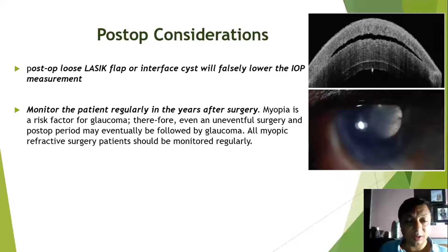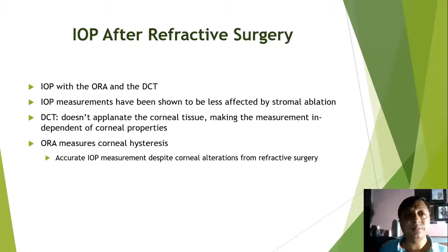Now, the Goldmann applanation has limitations. If you look at newer tonometers like the ocular response analyzer or the dynamic contour tonometer, they have a little advantage over the Goldmann. They have been shown to be less affected by the ablation. So DCT doesn't affect the corneal tissue, making the measurement independent of corneal properties, and ORA measures corneal hysteresis. So these two may be a better technology. Of course, we require more data because there is a lot of research going on on hysteresis, but it requires more data on how to use it in day-to-day practice. But they have the potential to be used in day-to-day practice for the longer term.